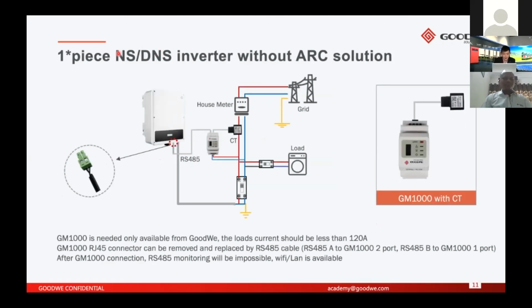And this one is also a single NS or DNS series inverter, but without the arc function. If the inverter is without the arc function, you need to order the GM1000 from GoodWe. GM1000 is this. It already includes the smart meter, the CT, and the cable between the smart meter and the CT. So it's also not so difficult, but the GM1000 will be more expensive than the CT. So I advise customers to order the inverter with arc function. If the inverter is without the arc function, the solution will be a little expensive, because you need to order the GM1000. GM1000 is a smart meter combined with the CT.